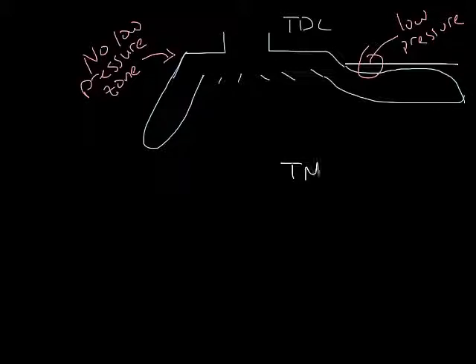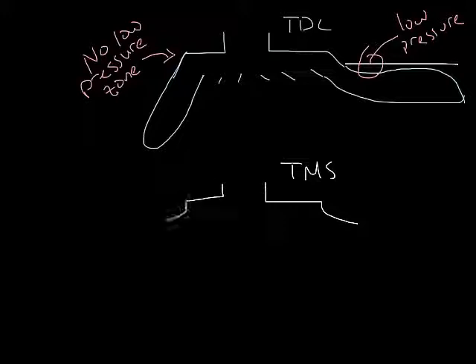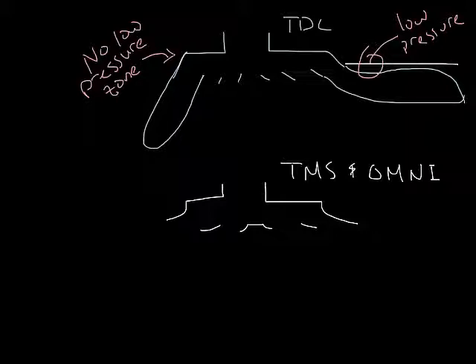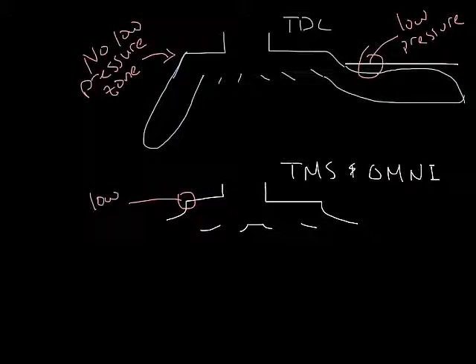Now if we look at the back pan of our TMS, another popular diffuser, it looks kind of like this with these little corners. This little corner creates an internal Coanda pocket where you have a low pressure zone inside the diffuser.